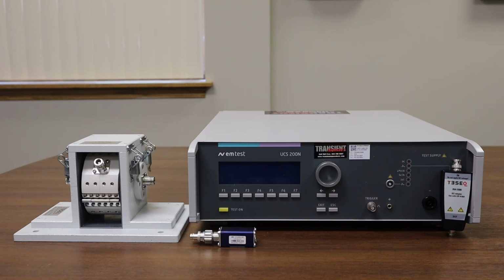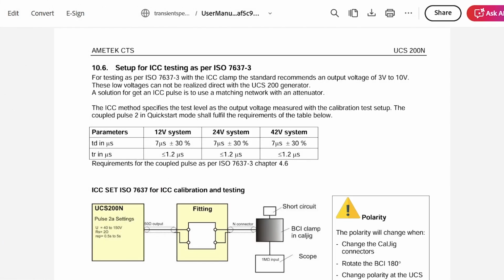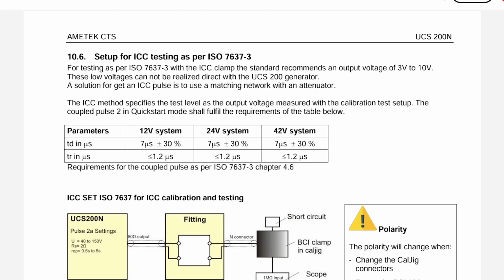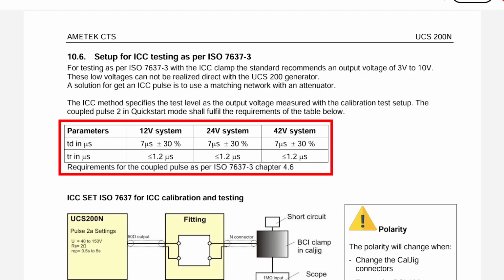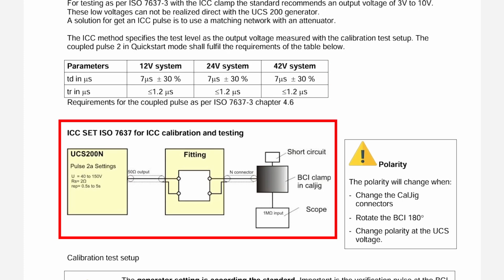Let's take a look at the setup for ISO 7637-3 testing and level setting using the ICC method. Now we're looking at the inductive coupling clamp information on page 54 of the user manual for the EMTest UCS 200N. At the top, we have a brief overview, and just below that a table for the requirements for the pulses with the different systems. Below that we have a setup diagram for the ICC calibration or test level setting, as well as testing.